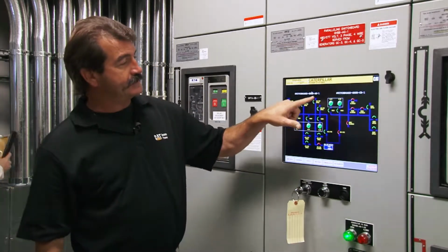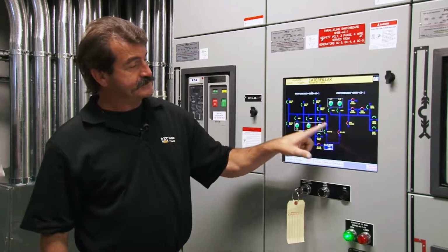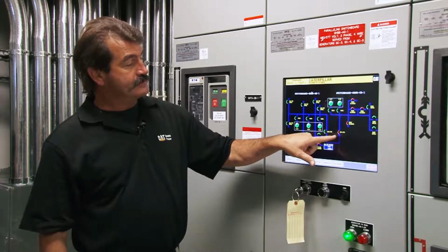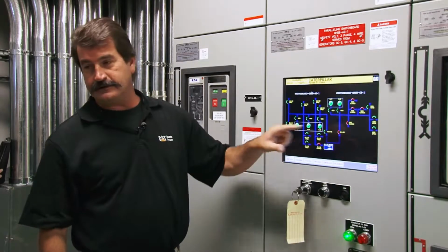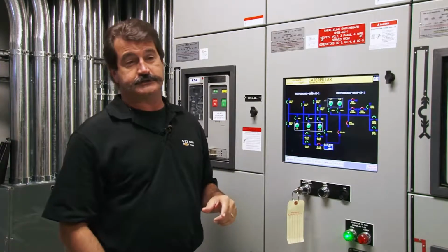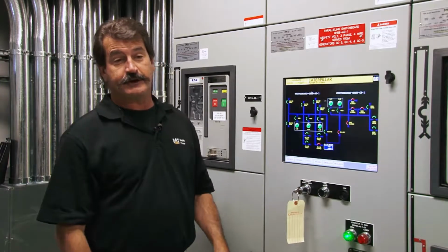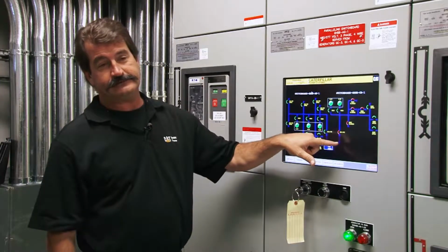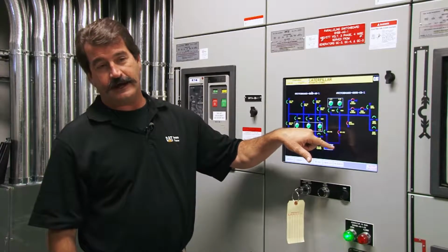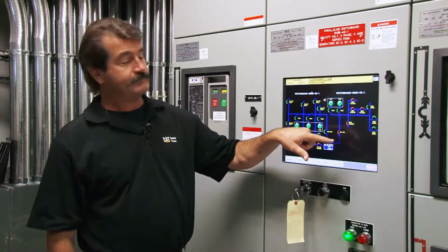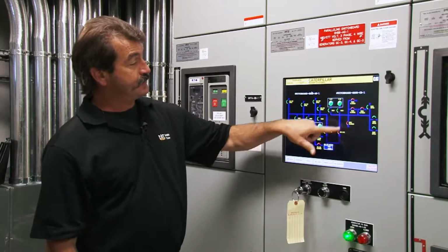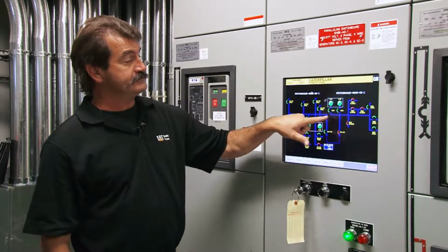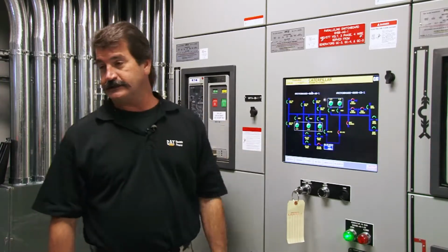What we've done is taken the original gear, and that's on this side of the screen. This tie breaker right here used to be the generator 3 circuit breaker down there. We've converted that into a tie breaker, a normally closed tie breaker, and that's what connects the two gear, the gen bus here and the gen bus here, together.